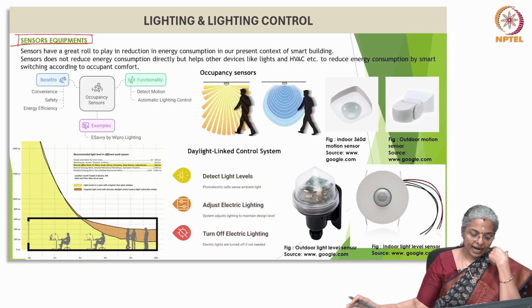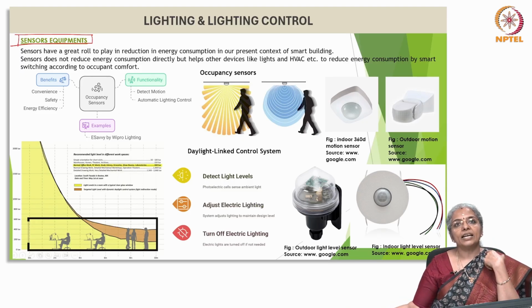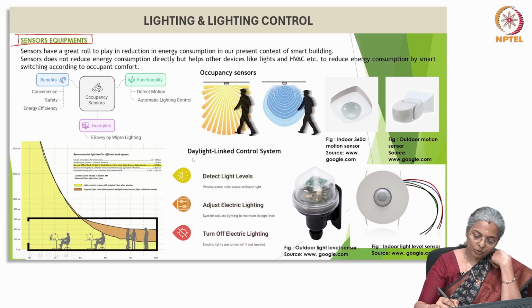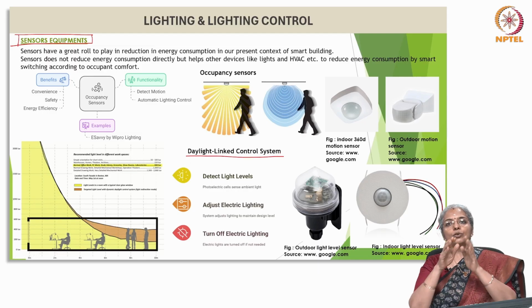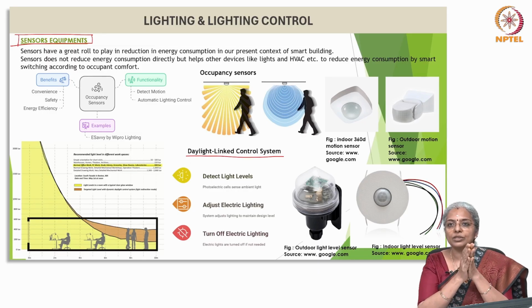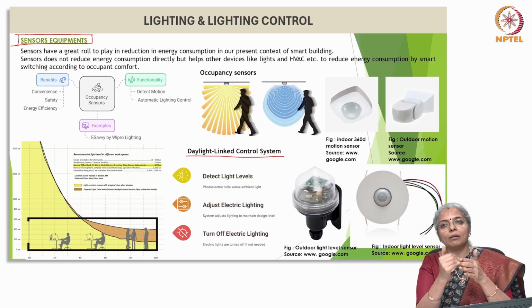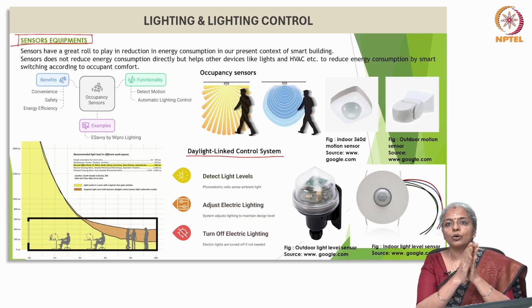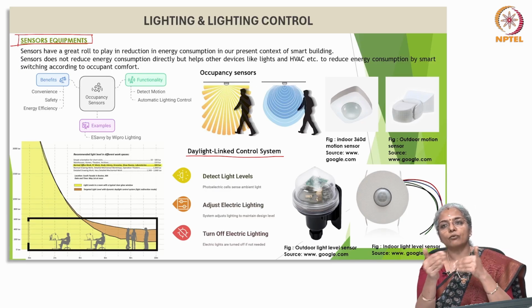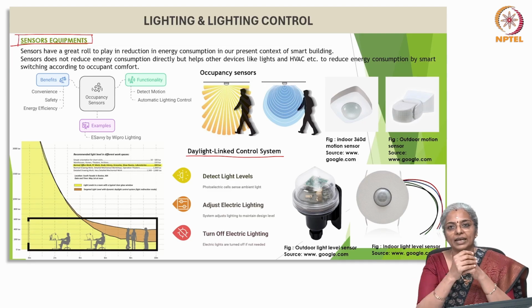Next is daylight linked control. What is a daylight linked control system? Photoelectric cells can be used either simply to switch lighting on and off or for dimming. They could be mounted either externally or internally. It is very important to incorporate time delays into the control system to avoid repeated rapid switching, which could be caused by fast moving clouds or similar factors.